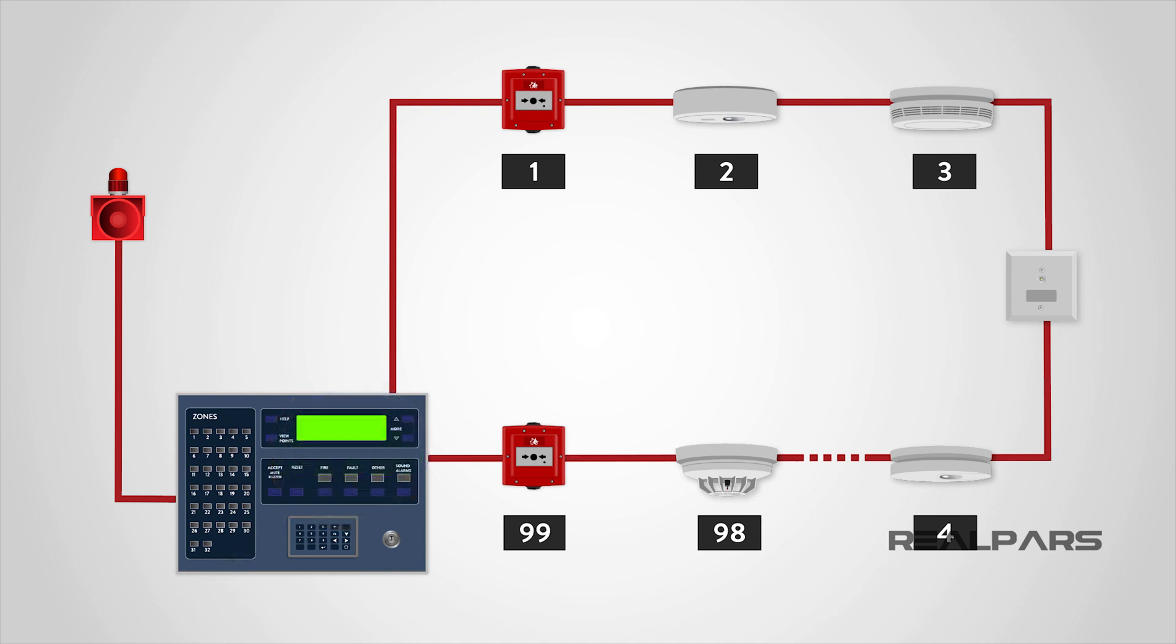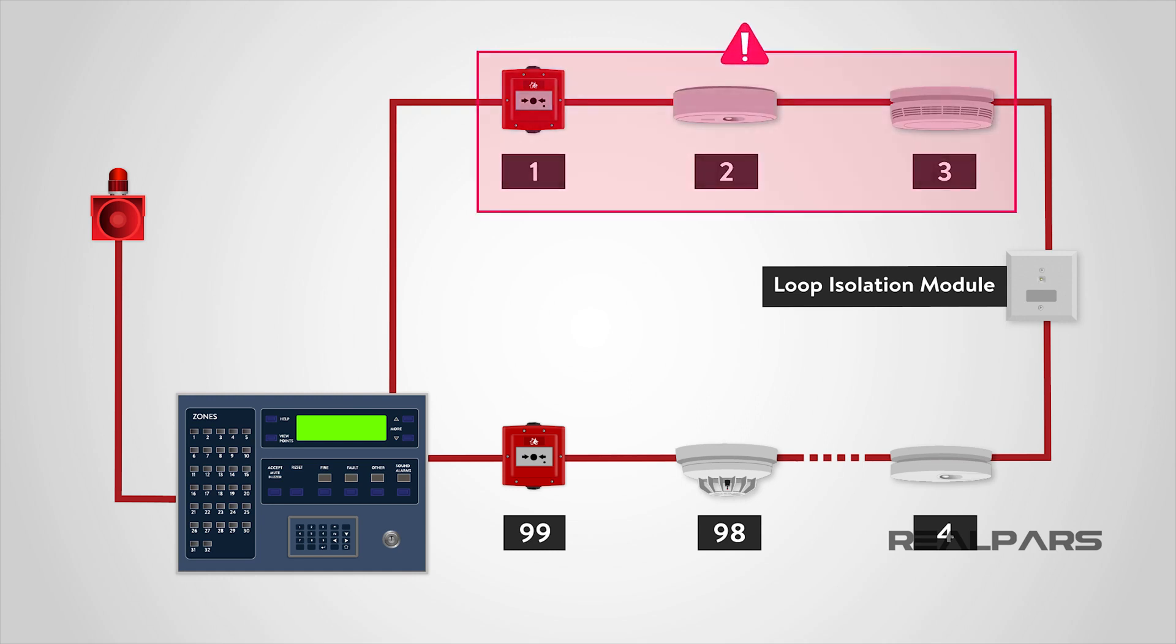The detection circuit is wired as a loop, and up to 99 devices may be connected to each loop. It is common for the loop to be fitted with loop isolation modules so that the loop is sectioned in order to ensure that a short circuit or single fault will only cause the loss of a small part of the system, allowing the rest of the system to function normally.